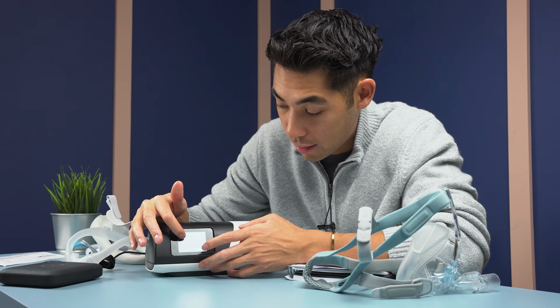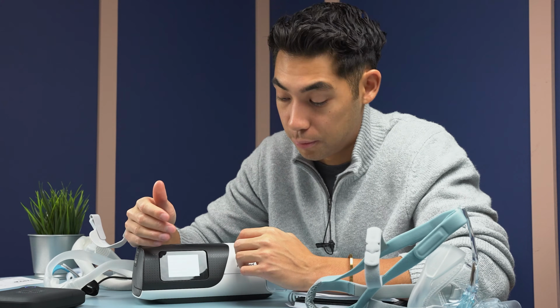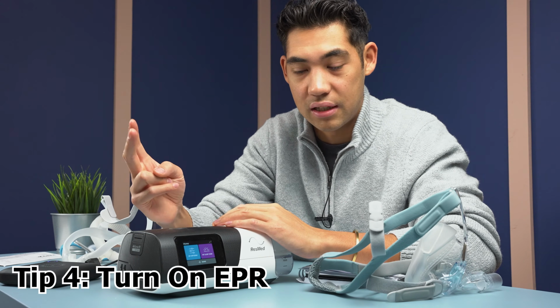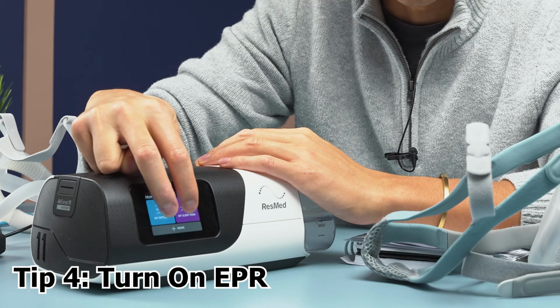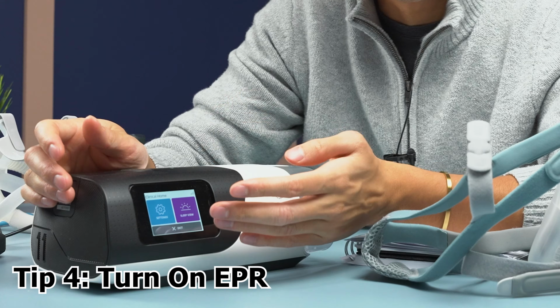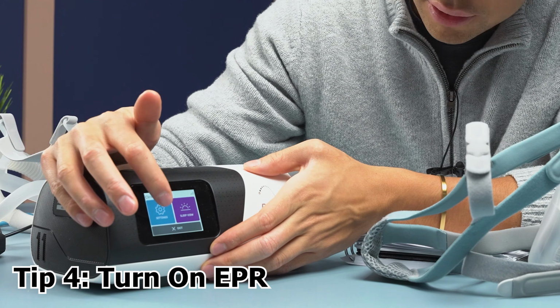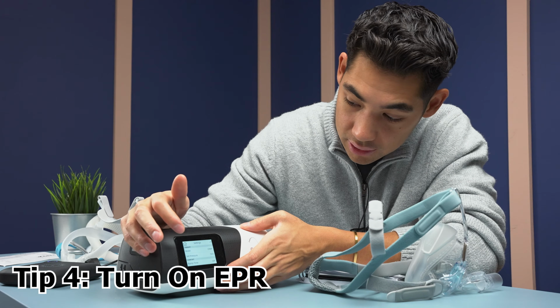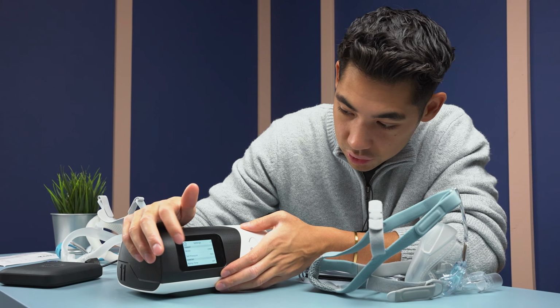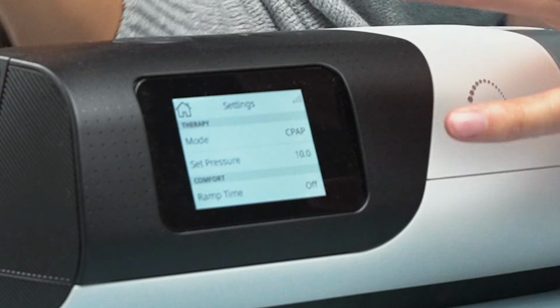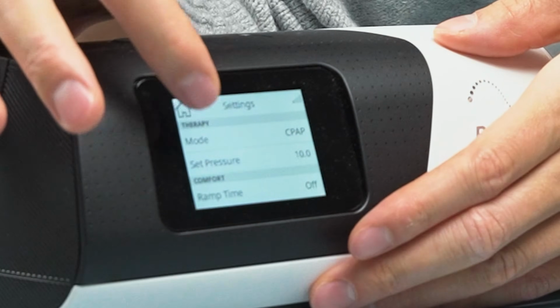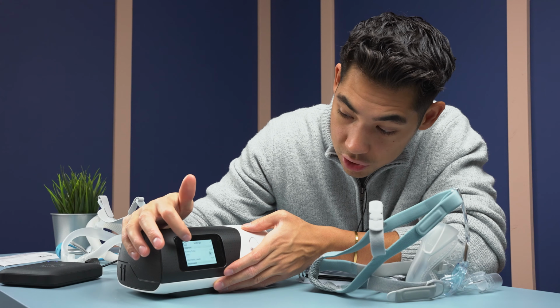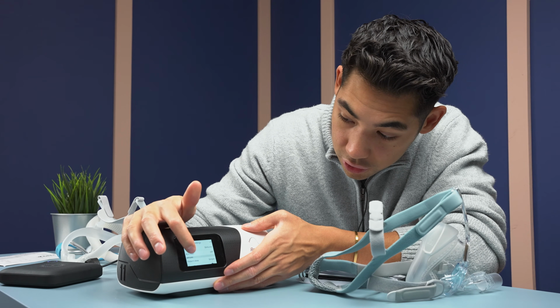Okay, so you can change the ramp time. You can also make it automatic or off. And I would definitely recommend having a small ramp time so that your body just gets used to that lower pressure, and hopefully you feel pretty sleepy by the time it gets to your prescribed pressure. Now, to get into your clinical settings, we're just gonna take 2 fingers and double click on the purple and the blue buttons, and you're gonna see this white clinical home menu area. And then we're just gonna click settings here. And we have set pressure, CPAP. You can change your CPAP mode to APAP, so automatic pressure, just continuous pressure, stuff like that. But what I want to show you here is our pressure relief settings.